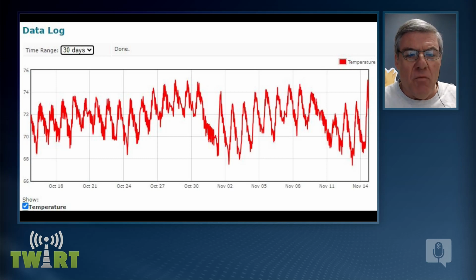One of the things I wanted to bring up, this 30-day one shows it more clearly. If you look around November 1st, the trend prior has a several degree fluctuation, then it drops into a whole different range. That's got to be where we made one of the changes, maybe where they repositioned the thermostats, or where it was actually brand new thermostats and one was bad out of the box and they changed it. But you can see the trend.